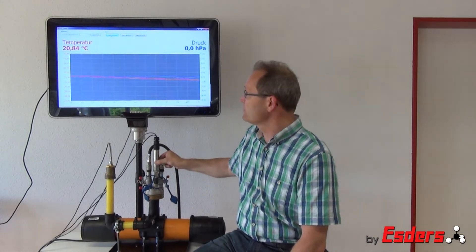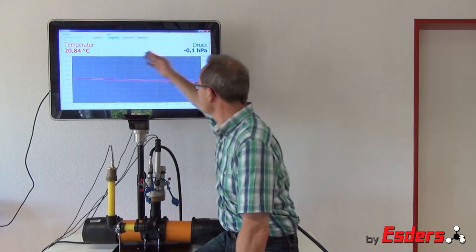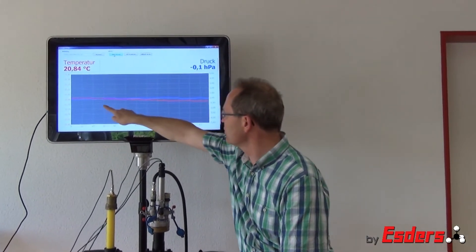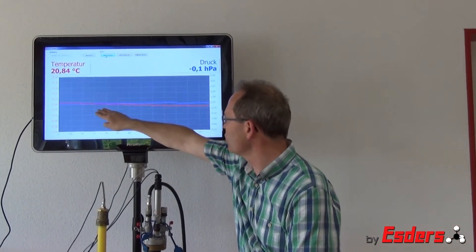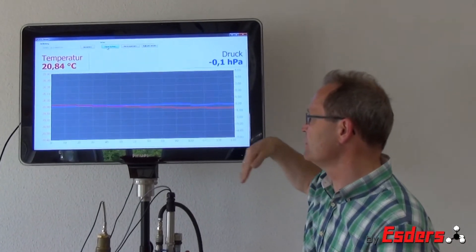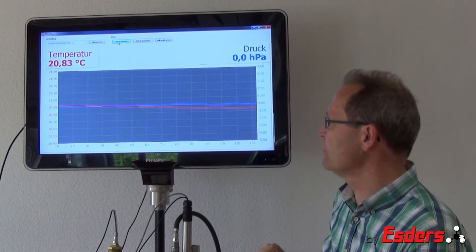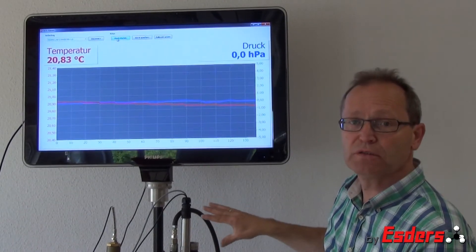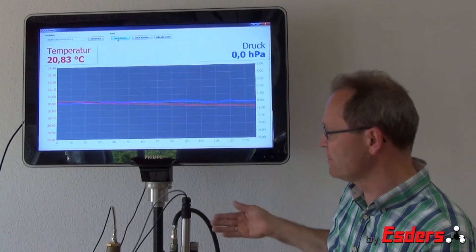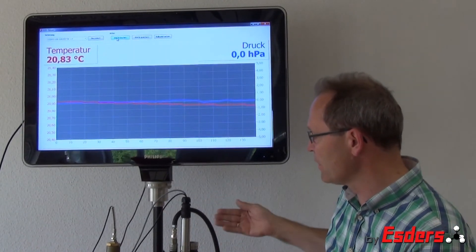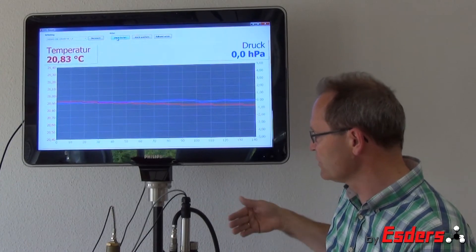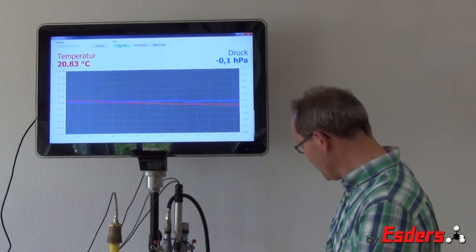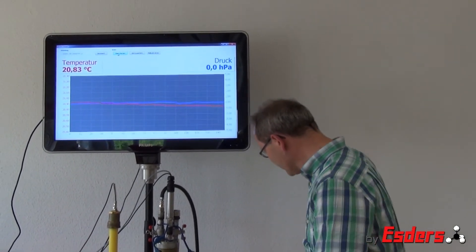Both values, the temperature and the pressure, are shown on this screen and we also show via a graph how the values will change over time. Now I'm going to put a system test pressure of about seven bars to the pipe, and this is done with this small compressing unit.